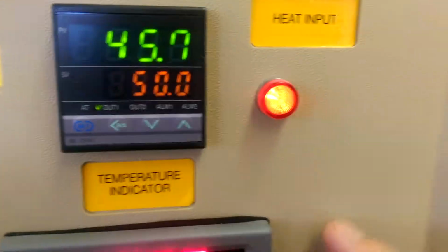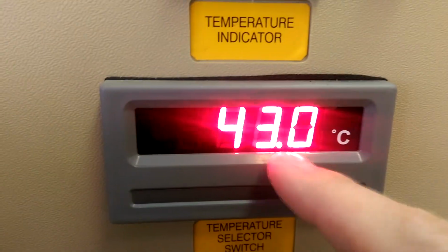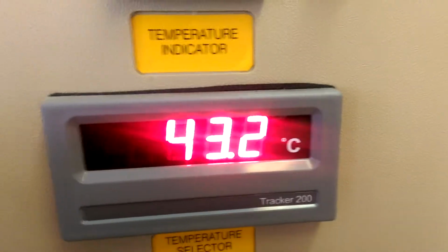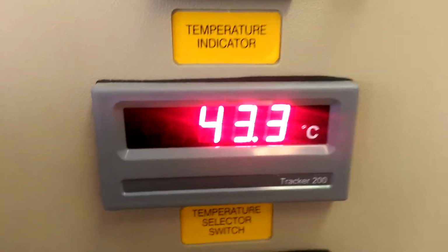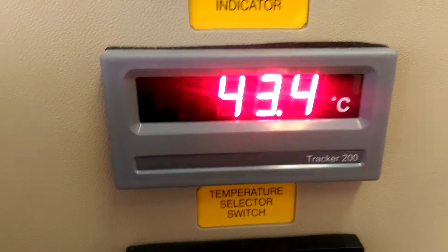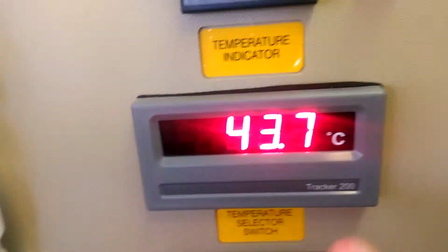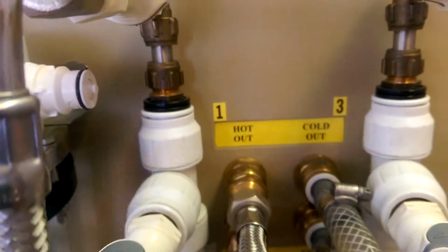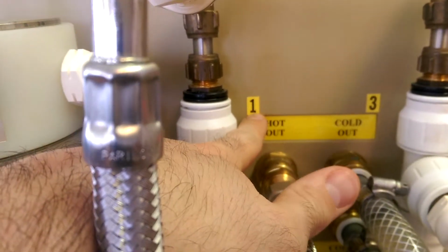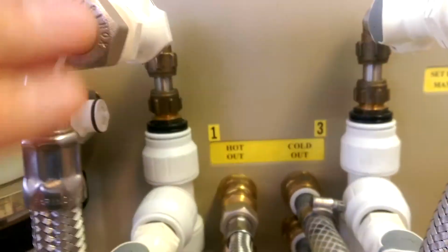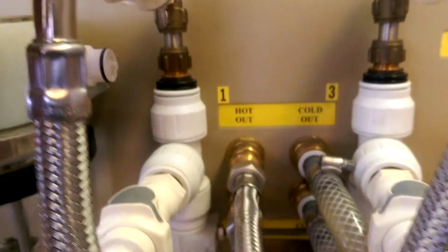You might ask, what's different between the temperature indicated here and the temperature indicated here? This is the temperature coming out of the hot water heater inside the unit. This is the temperature of the hot water exiting the unit. And there's probably about a foot to 2 feet worth of tubing between the exit of the hot water heater and the exit of the unit. This is the temperature you're actually concerned with for your measurements. T1, you can see, is measured here and indicated here. That is the temperature coming out of this unit, which is basically the temperature into the heat exchanger, the hot water in.